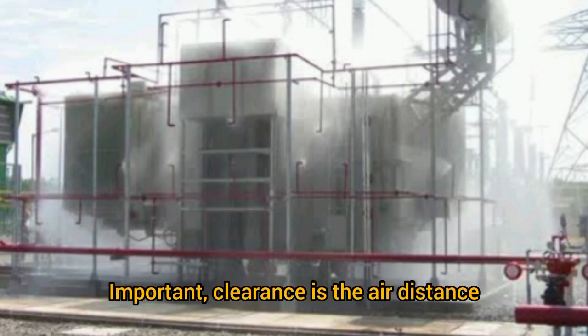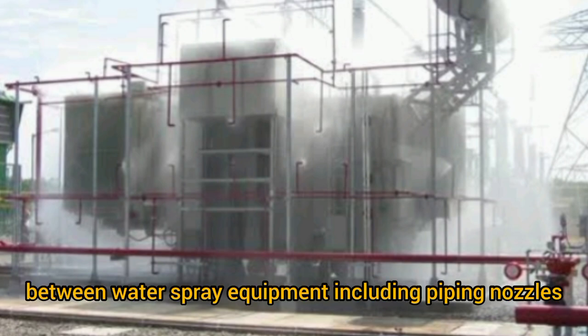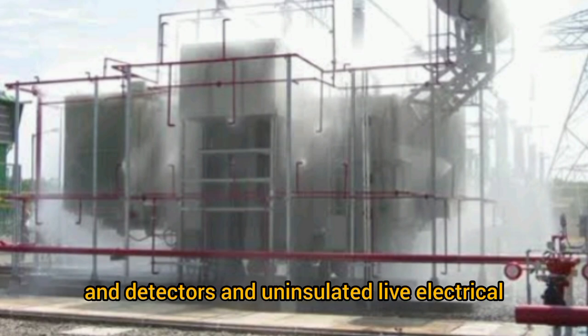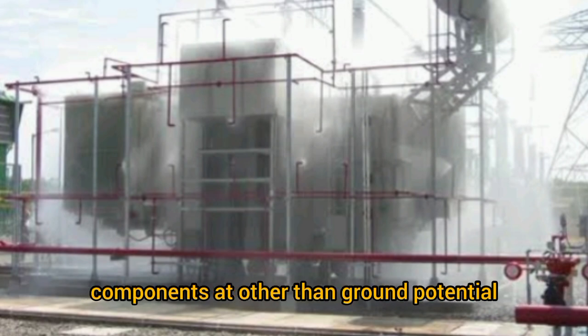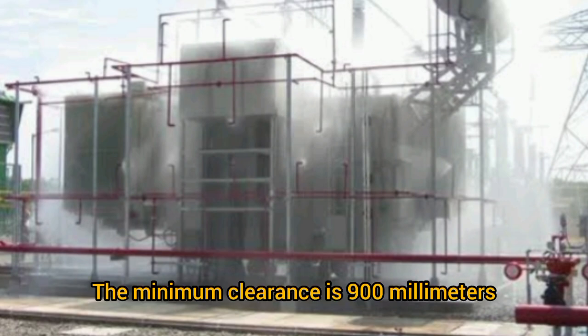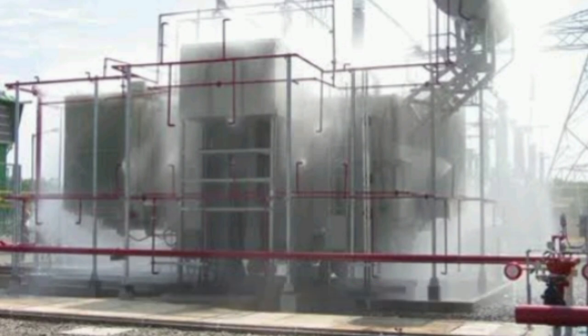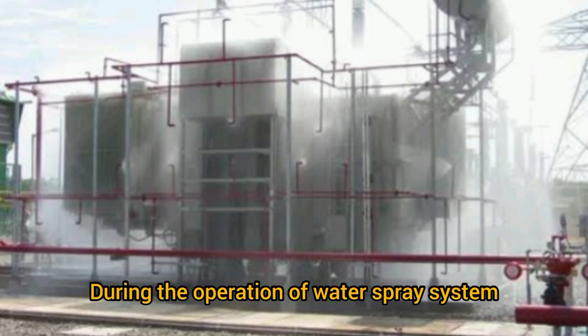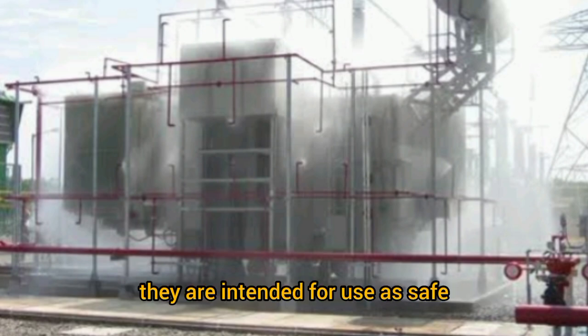Important: clearance is the air distance between water spray equipment, including piping, nozzles and detectors, and uninsulated live electrical components at other than ground potential. The minimum clearance is 900 mm under normal condition. During the operation of the water spray system, they are intended for use as safe.